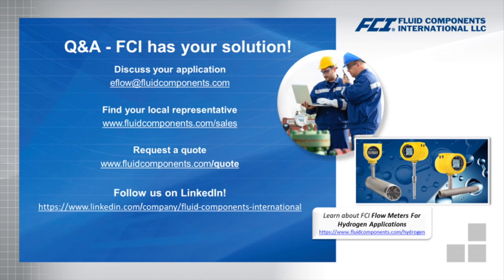We've been calibrating thermal flow meters in pure hydrogen and hydrogen hydrocarbon blends for decades now. The amount of heat transfer to the gas is not sufficient to ignite the gas itself. And the other thing is you also have to have the presence of air or oxygen in sufficient amounts. And this is not typically the case when we're dealing with these types of process measurements.